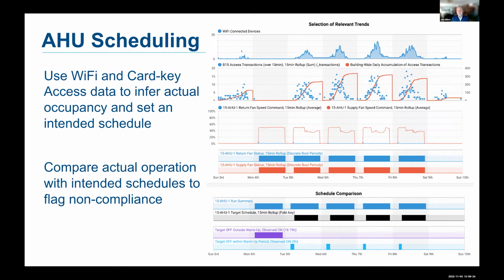So you can see the two items up here is the Wi-Fi trend and then the card key data. Then we can compare actual operation of the air handler, this is what we see in the middle, to our target schedule or our intended schedule that we developed. And then we can flag areas of non-compliance. So are we seeing the air handler operating well outside the schedule and well outside the warm-up period for the schedule?